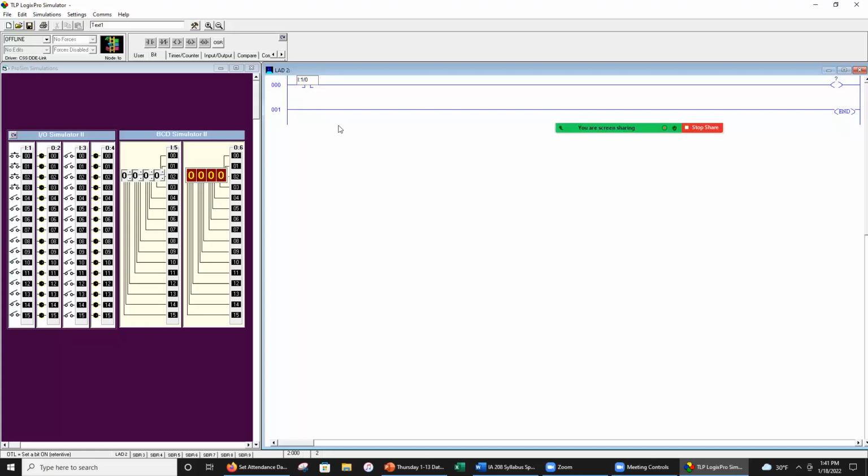I means input, :1, that means slot one. And we're going to get into what slot means, but in PLCs, generally you can have multiple slots where you can add inputs or outputs. In the simplistic PLCs that we're going to be using in class, the MicroLogix 1000, they've got generic slots, even if they aren't physically using a rack with slots. It's just called a slot for where they've installed the IO internally. But each IO grouping has got a slot number. In this case, we've got four slots. First one's inputs, the second one's outputs, third one's inputs, and the fourth one's outputs.